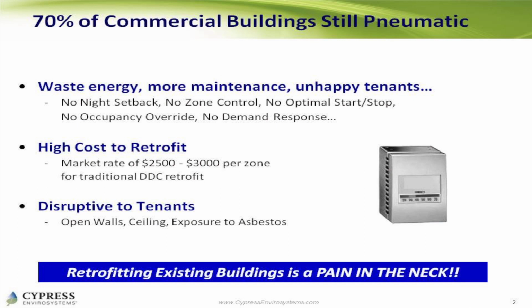have out there, which, believe it or not, is primarily, or 70% of our existing commercial buildings are pneumatically controlled, which means that to move the valves and the dampers to control the amount of air and the temperature of the air coming into a room, it's actually not an electric signal, it's compressed air that's sending the signal and making those things move. It's very reliable and solid, robust technology that is about 100 years old. So it's prevalent, it works, but it does not give any feedback. So you're sending compressed air out there, out to office spaces, and you're hoping that it's keeping the temperature.